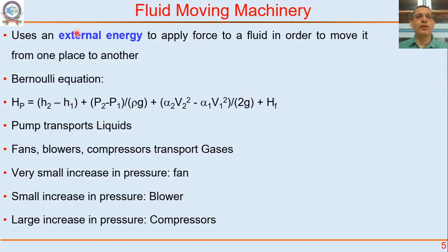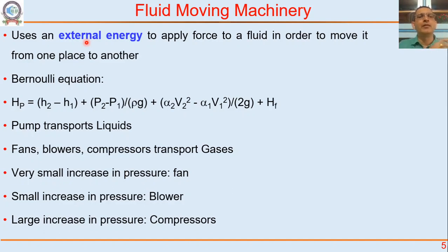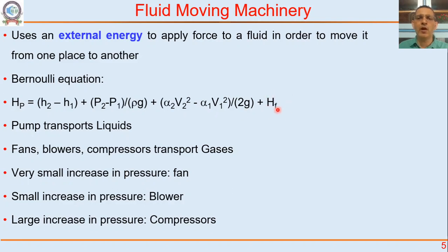Recall from your Bernoulli equation lectures that fluid moving machinery — either a pump or a compressor — uses external energy to apply pressure, to apply force, to give energy to the fluid, which is then at a higher pressure and able to go through the pipeline. This device is converting external energy — electrical energy into mechanical energy — and giving that energy to the fluid. The pump head required equals the hydrostatic head to be overcome, plus pressure head, kinetic head to be imparted, and head lost due to friction.